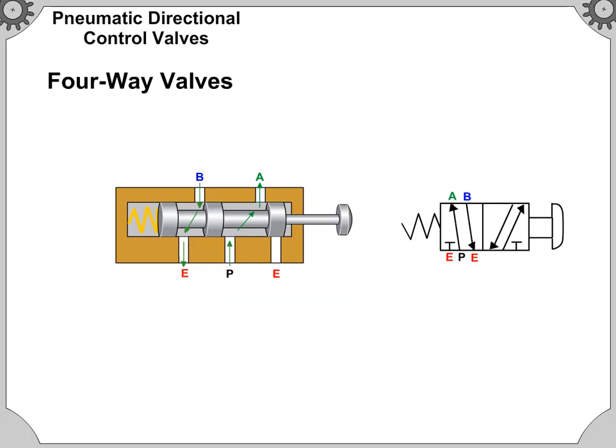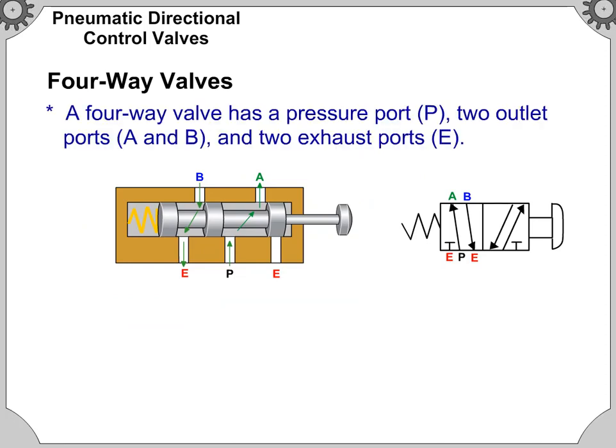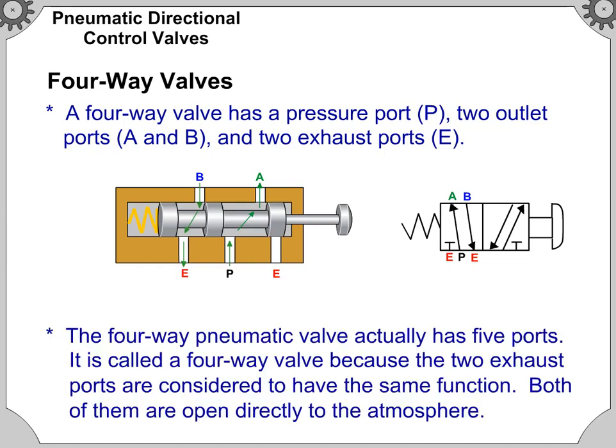A four-way valve has a pressure port P, two outlet ports A and B, and two exhaust ports E. The four-way pneumatic valve actually has five ports. It is called a four-way valve because the two exhaust ports are considered to have the same function — both of them are open directly to the atmosphere.